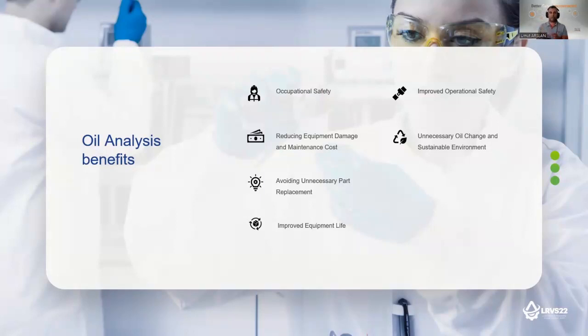An example again from transformer oil analysis: monitoring combustible gas rates, that's important. It's called DGA, dissolved gas analysis, because higher rates indicate arcs and sparkings: acetylene, ethylene, carbon dioxide, methane gases. That's really important to follow the trends.